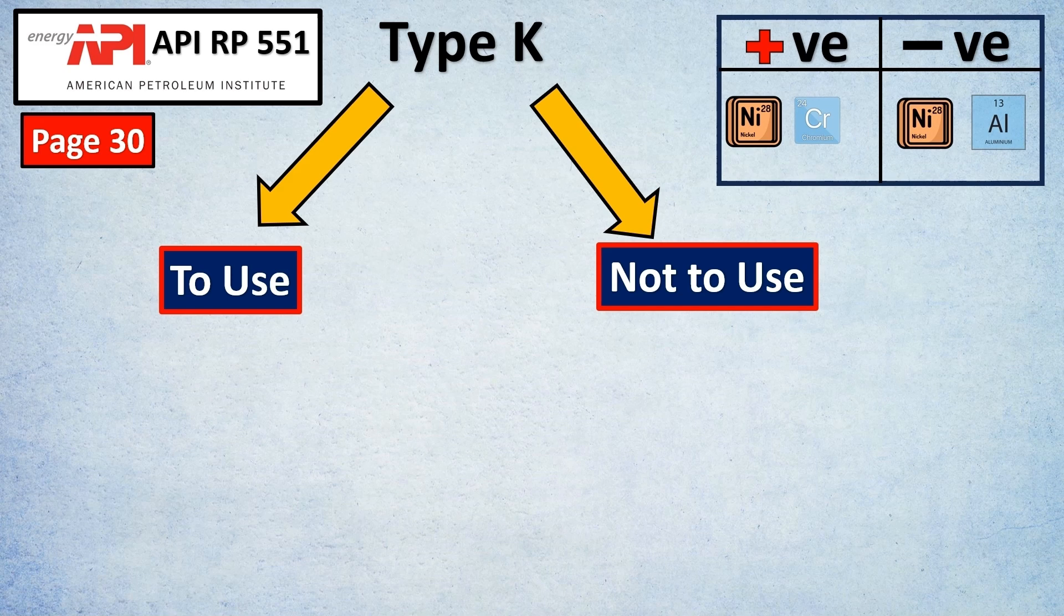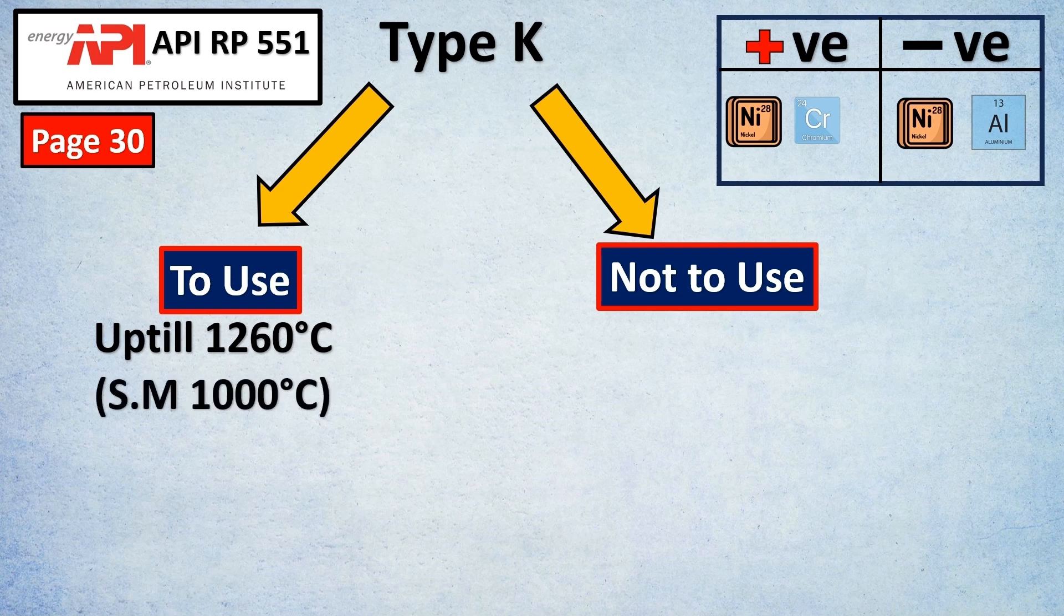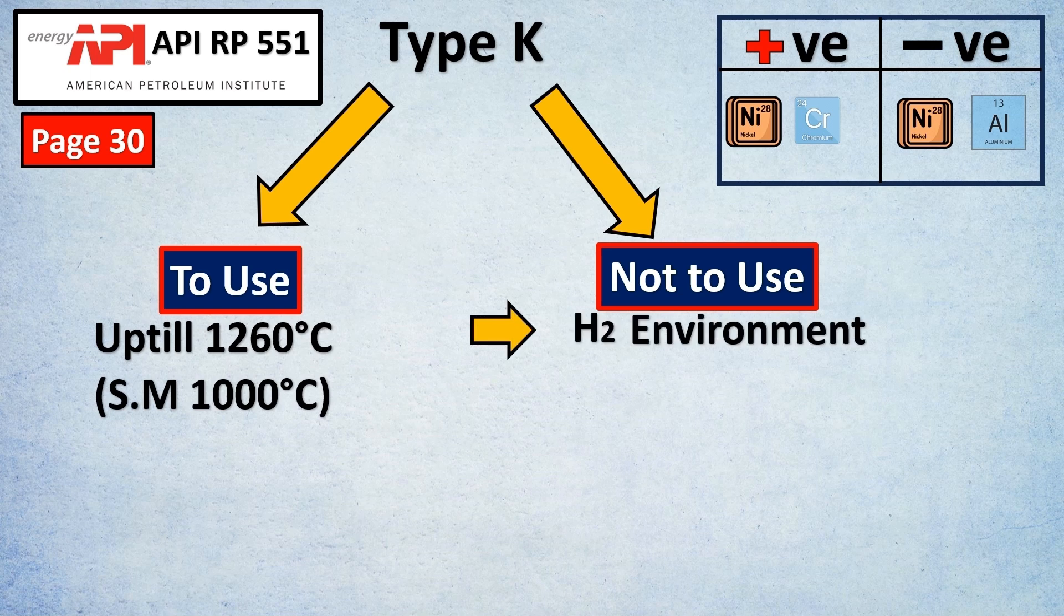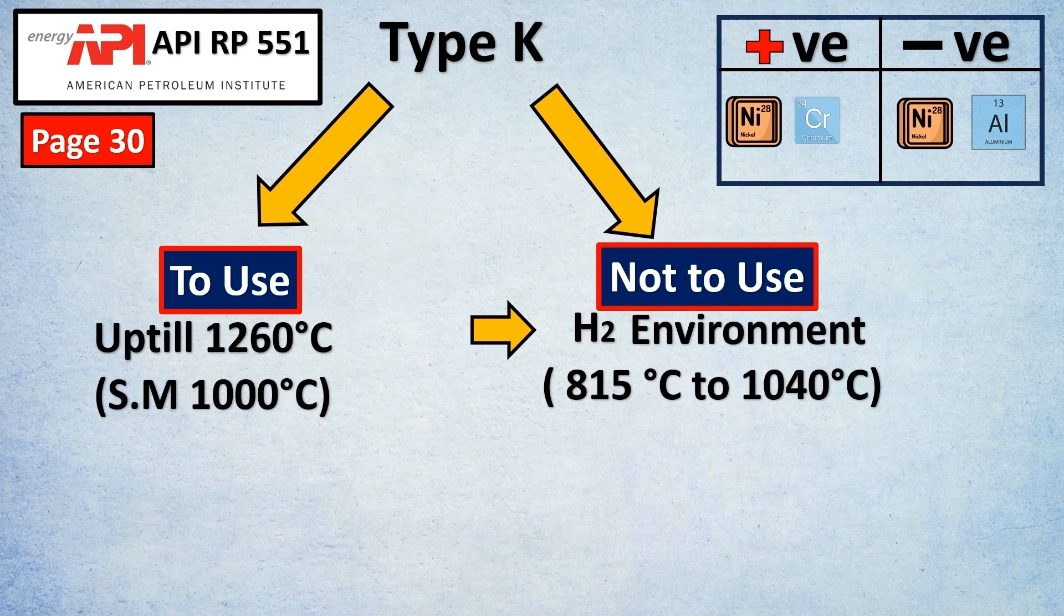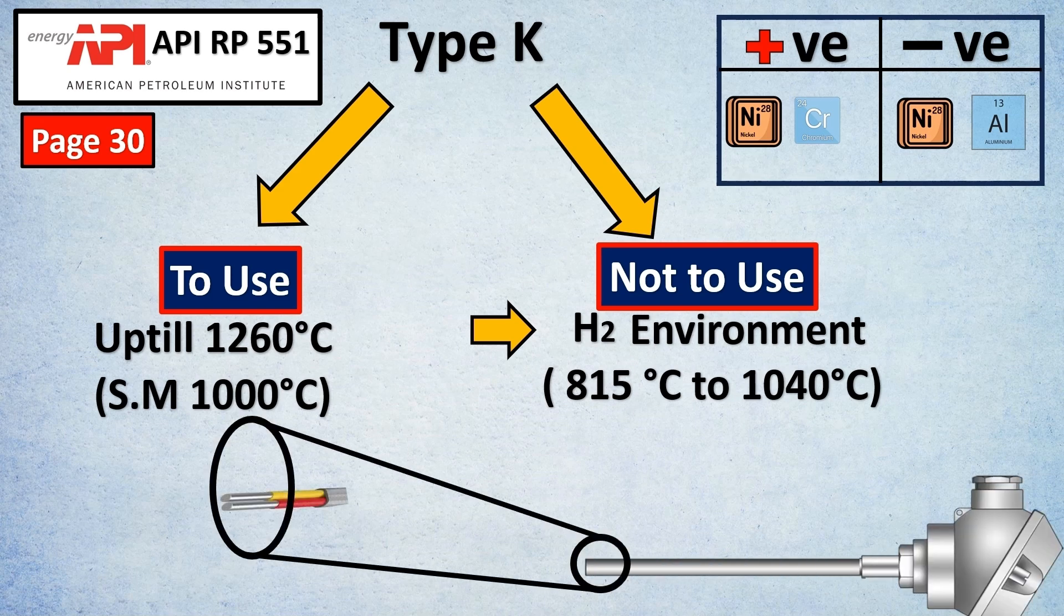Type K can be used up to 1260°C, but as a safety margin I personally recommend around 1000°C. You cannot use this in H2 environment as per API RP standard, especially between 815°C to 1040°C. Why? Because at such high temperatures, hydrogen breaks down and the H molecules hit the sheath and enter inside the thermocouple, damaging it and giving false readings.